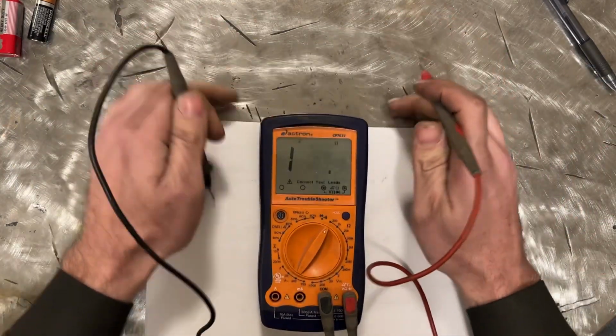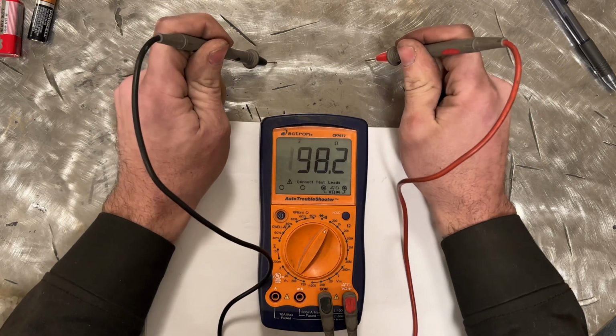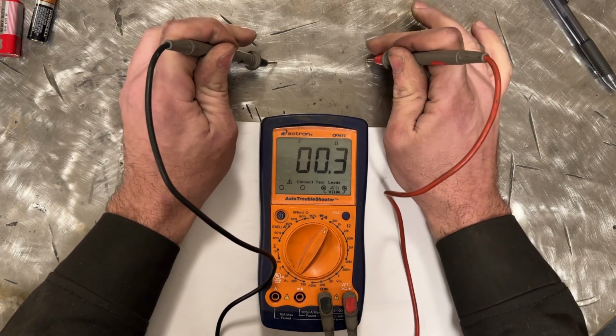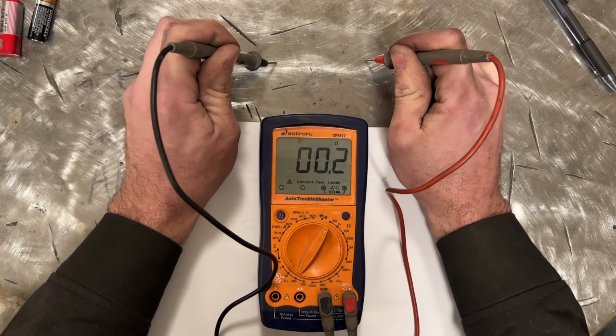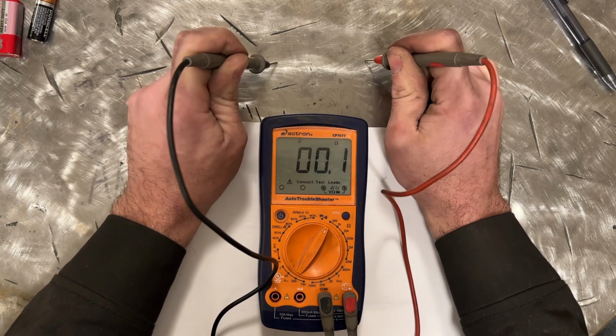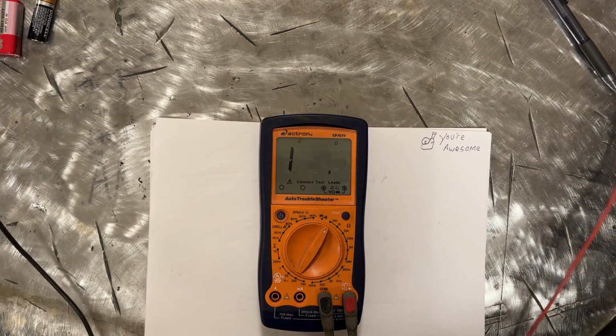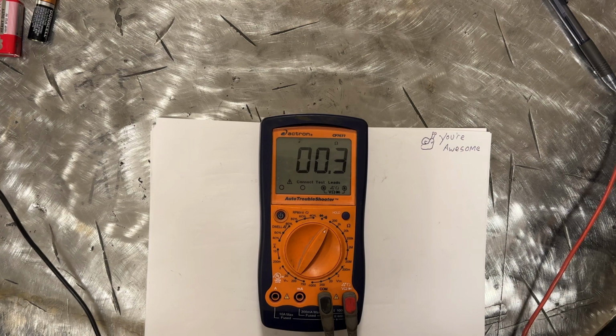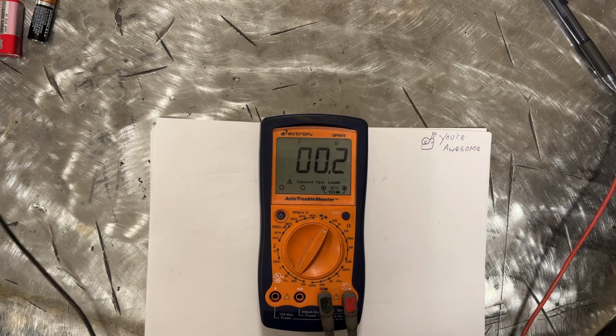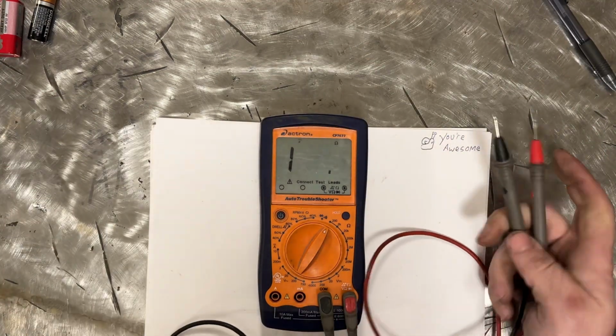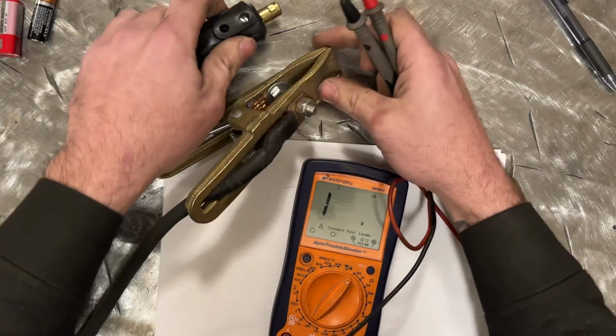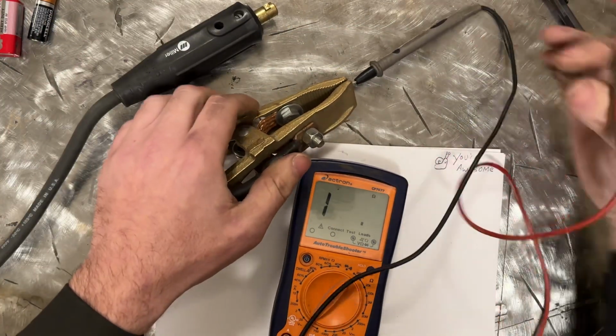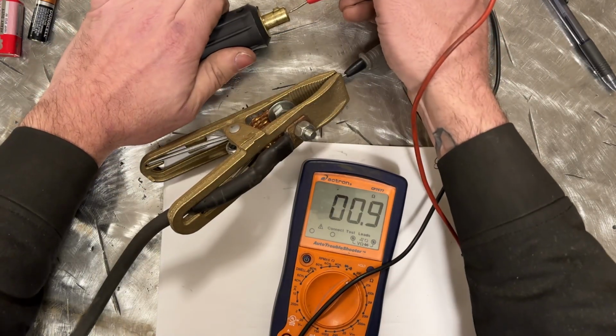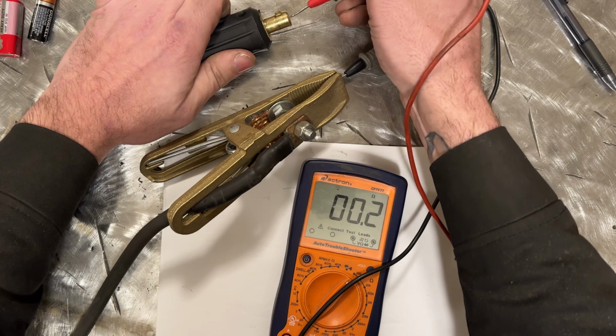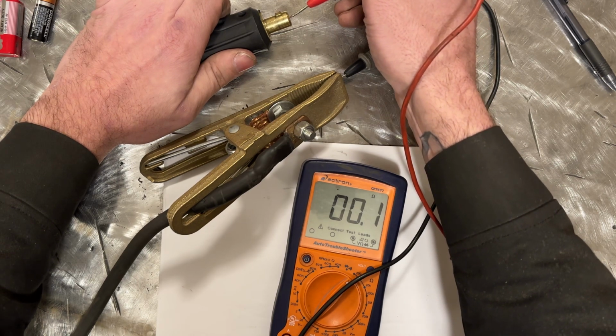Now let's start by testing something very simple. This is a very thick steel table. Our resistance from the positive to the negative should be very low, and it is. It's pretty much the same as just touching the tips together. And I'll go all the way from opposing sides of the table. Again, very low resistance, which is what is to be expected. It's forming a path right through there of very low resistance. I'm going to check the ground cable on my welder. And this also should have very low resistance. And it does, very much the same as just touching the tips together.